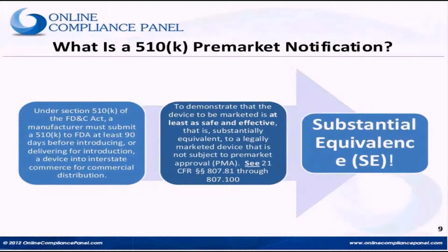Now, let's briefly talk about what a 510K premarket notification is. We talk about the 510K section of the FD&C Act, but what is the requirement to meet this section? You have to demonstrate that your device to be marketed is at least as safe and effective as a legally marketed device. That talks about substantial equivalence, and that's what we are going to focus on today.